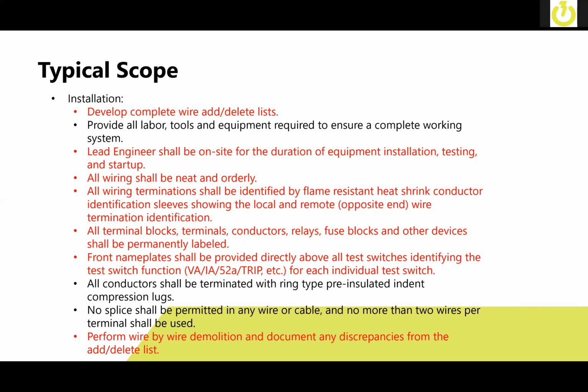Wiring shall be neat and orderly whenever we install new labels and new equipment. All the wiring back to the next point of termination is all new. Sometimes people go in and just clip the wire, relug it, and land it back on the new device. That can lead to some issues later on in the field where you're trying to troubleshoot or do some event analysis and it doesn't match what it should from a design standpoint.